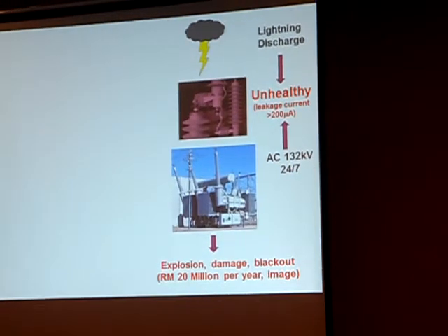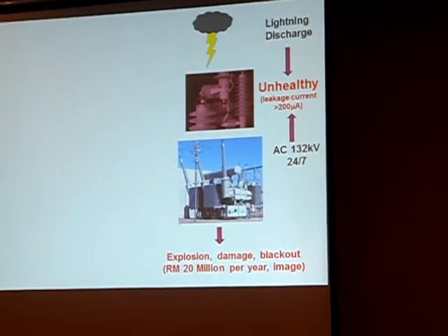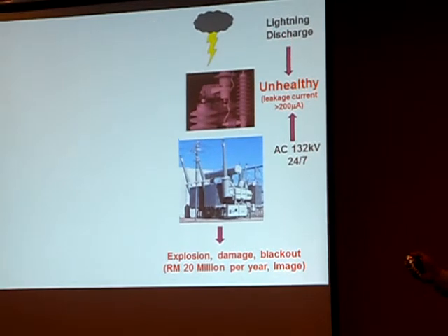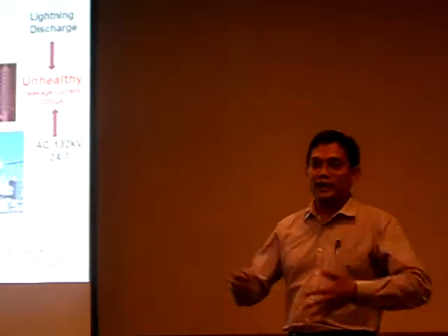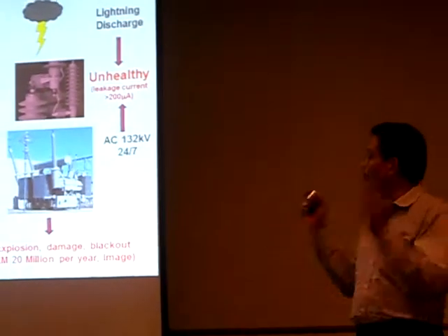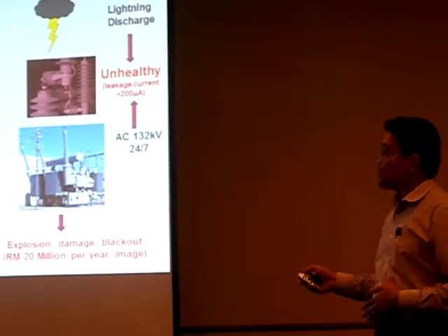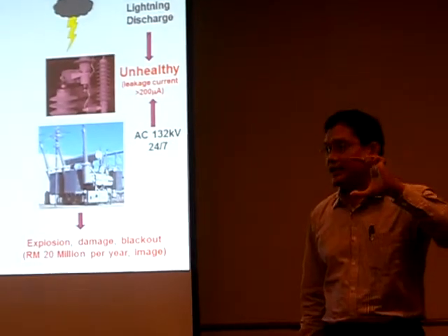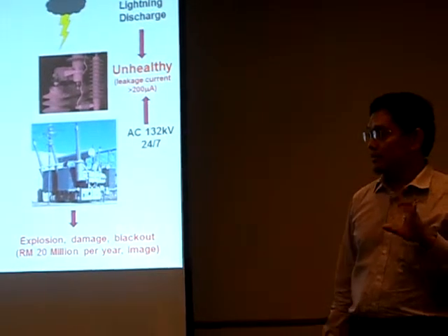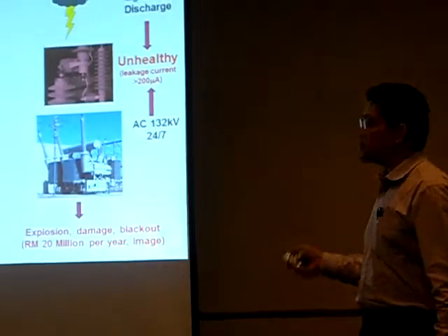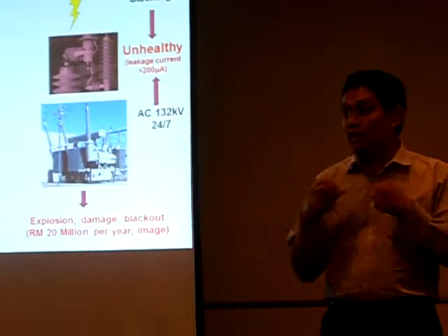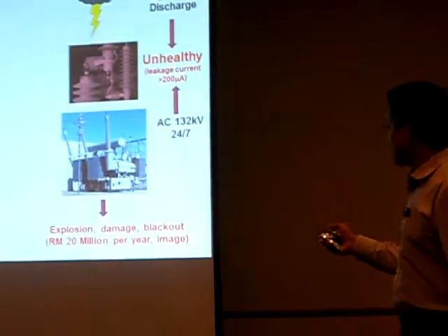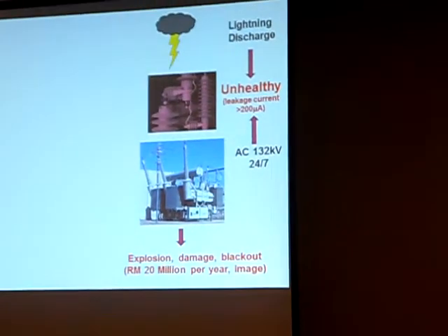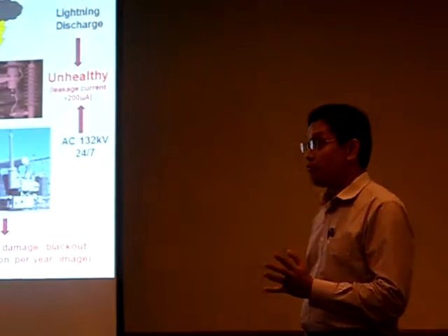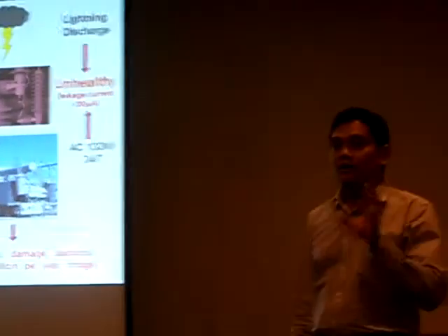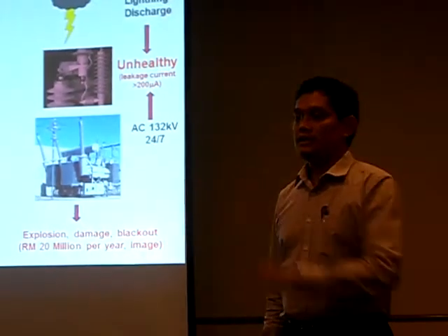But this only works provided the arrestors are healthy. Over time they age due to discharge activity. More lightning means more aging and degradation, and since they're connected 24/7 across the AC voltage, this causes a small leakage current to flow. With certain technology we own, we can detect this leakage current using a specialized circuit or software, with a cutoff point where we can say this arrestor is bad.